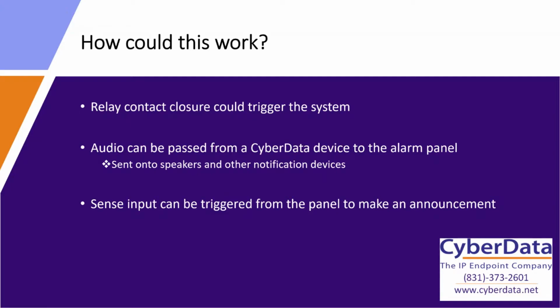But like I was saying in one of the initial examples, it can also work in the inverse, where the CyberData product doesn't necessarily need to activate the alarm. The CyberData device can be activated by an alarm going off, and you get that kind of automatic capability that you don't really get with our products. Our products are smart, but we don't really have any sensors yet that can detect, say, things like glass break or just a regular smoke detector or a vape detector or anything like that. And by pairing the sense input on a CyberData product, the inverse of a relay, where it's not actually closing but expecting something else to close, can be triggered from that same fire alarm panel.